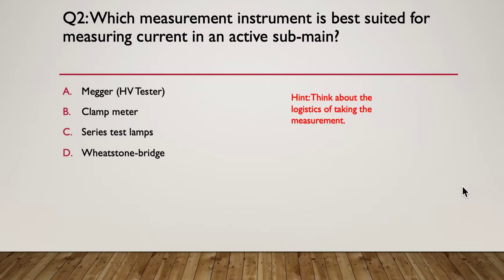Hint: think about the logistics of measuring current in an active sub-main. The answer is a clamp meter — it can be slipped around a cable while it's live without breaking into the circuit. A Megger or HV tester would be inappropriate, series lamp tests don't measure current, and a Wheatstone bridge measures very low resistance. If you didn't know the exact answer, elimination would bring you to the clamp meter.